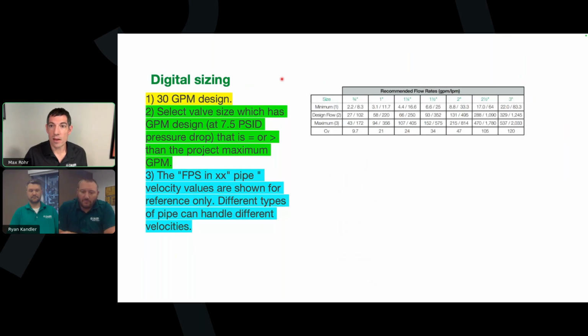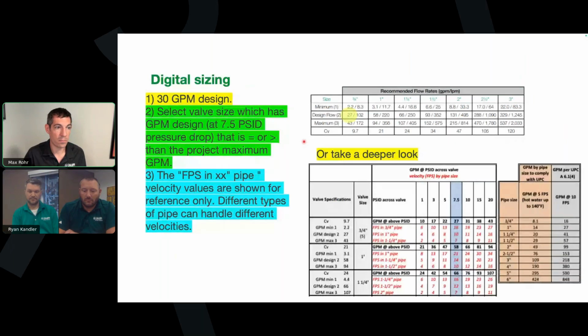Okay. We then will get a follow-up question sometimes and they'll say, okay, wait a second, you're telling me we're going to move 30 GPM through 3/4 inch pipe. That's what we're saying with the easy chart here, that if you want to move 27 GPM at design flow through a 3/4 inch valve, this is the one that you would pick. What does that actually mean if we get into the velocities of the valve? So if you guys were going to go out into the field and pipe a hotel and the engineer says we need 30 GPM to go out to the building, and you said, hey, we can save a lot of money if we pipe this entire building with 3/4 inch pipe, what would you expect to maybe happen in that scenario?